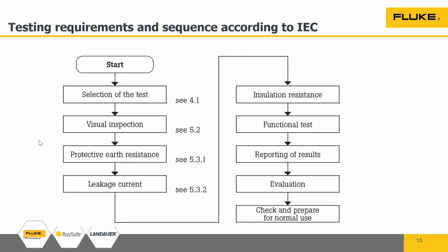Okay, so this is a simple flow chart that we have made. When you have a device under test, that is any medical device, and the electrical safety test equipment, what I'm showing here is part of the electrical safety testing of a medical device. When you talk of a medical device, you need to test electrical safety.